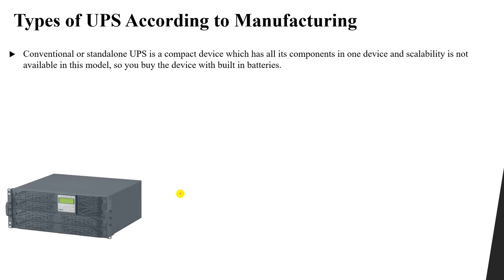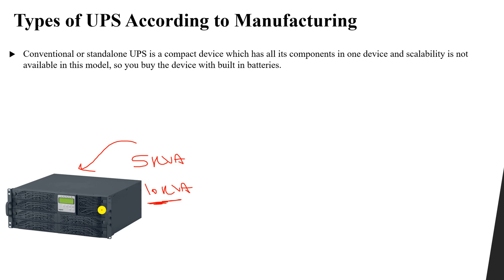In this lesson we will talk about the difference between the conventional UPS and the modular UPS. The conventional UPS, or stand-alone UPS, is a compact device where all components — such as batteries, inverter, and rectifiers — are contained in one compact unit. This device can be, for example, 5 kilo volt ampere or 10 kilo volt ampere — one big unit with a constant fixed rating. This type of UPS is not scalable, meaning its rating cannot be increased. The built-in batteries are inside it to store and provide electrical power when AC power is not available.